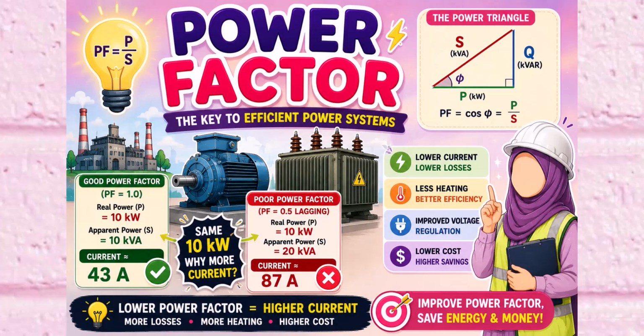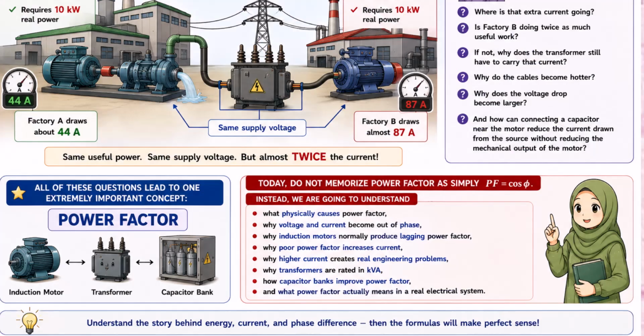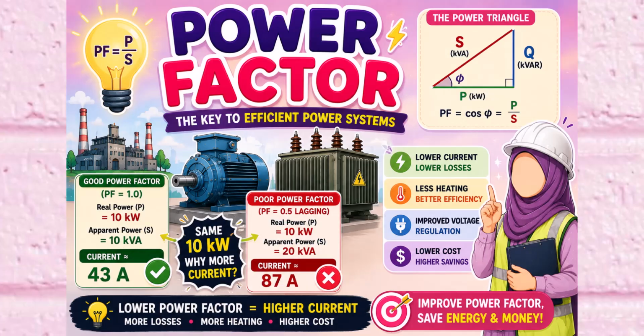Today, do not memorize power factor as simply power factor equals cos phi. Instead, we are going to understand what physically causes power factor, why voltage and current become out of phase, why induction motors normally produce lagging power factor, why poor power factor increases current, why higher current creates real engineering problems, why transformers are rated in kilovolt ampere, how capacitor banks improve power factor, and what power factor actually means in a real electrical system. The goal of this lesson is not to memorize another equation. The goal is to understand the physics behind power factor.